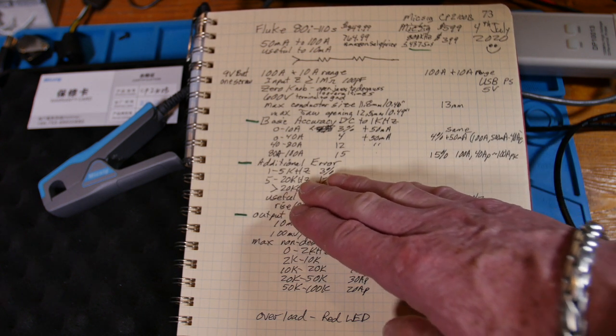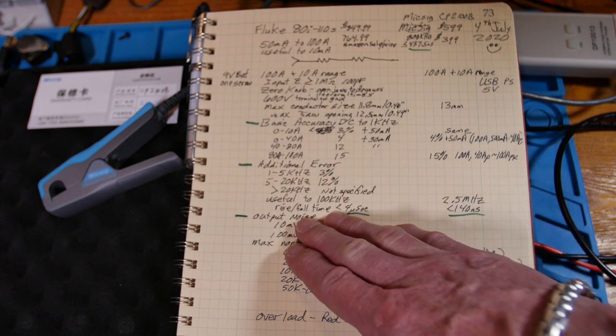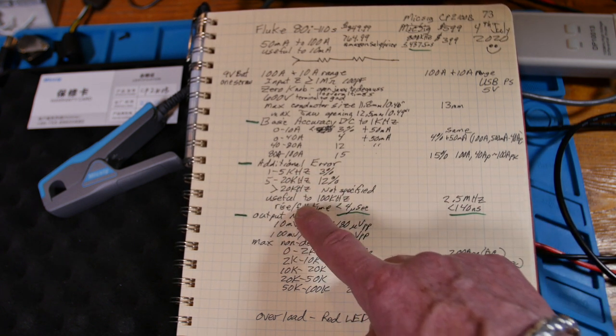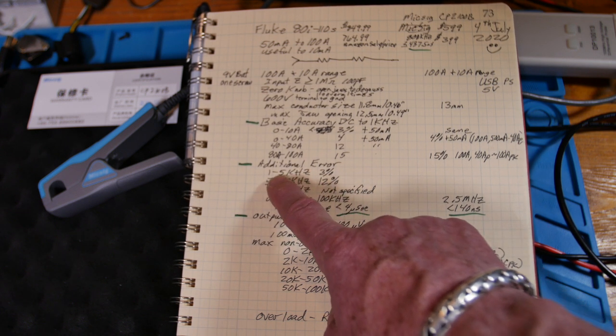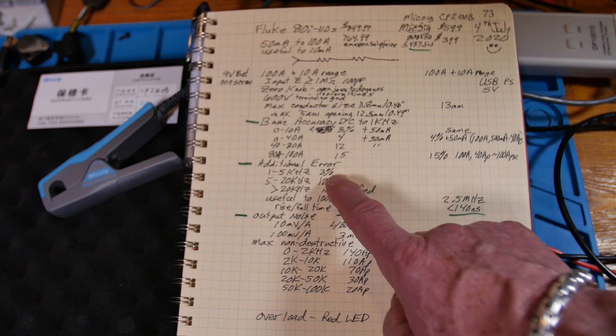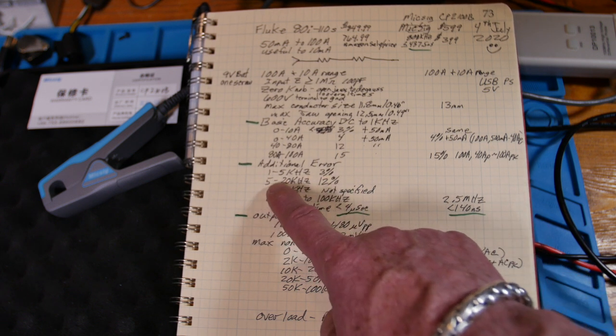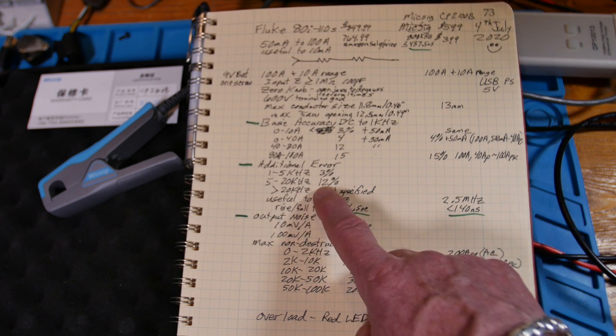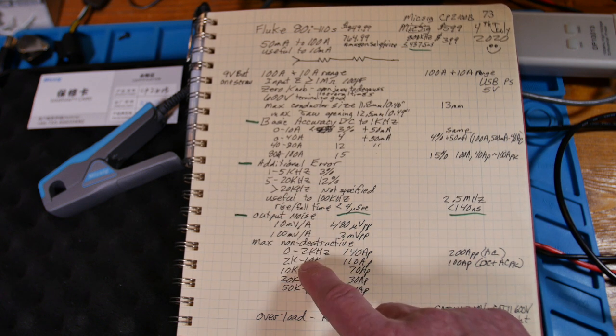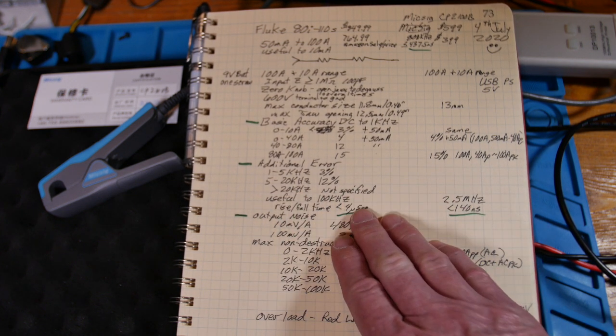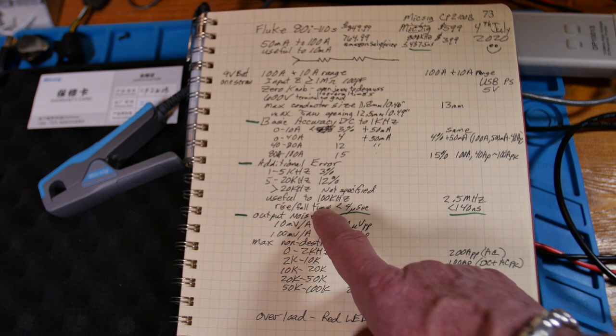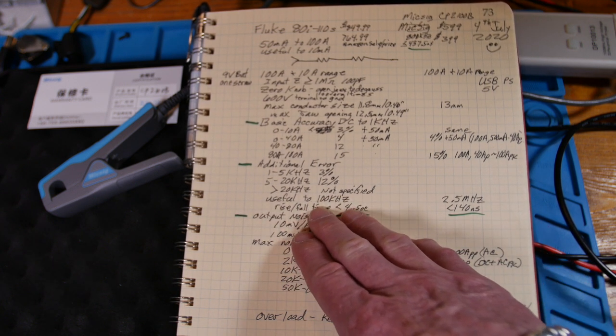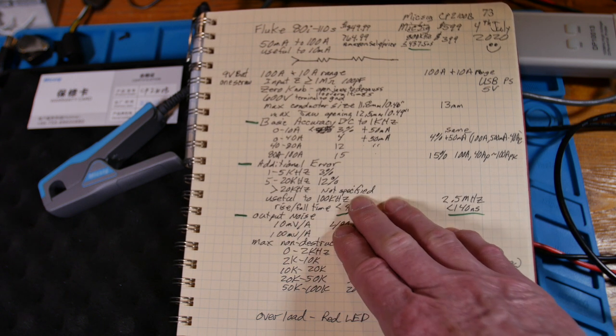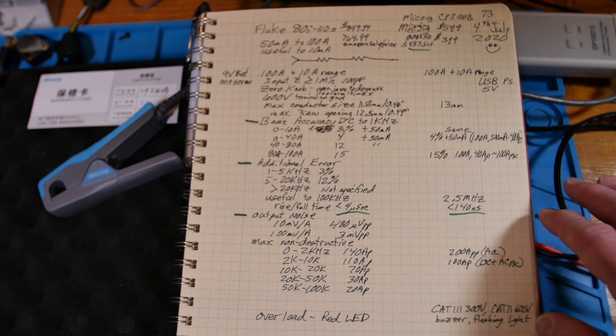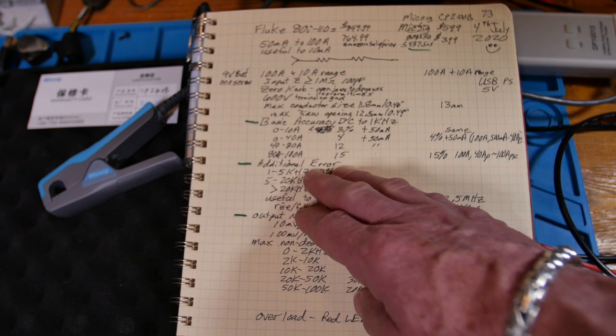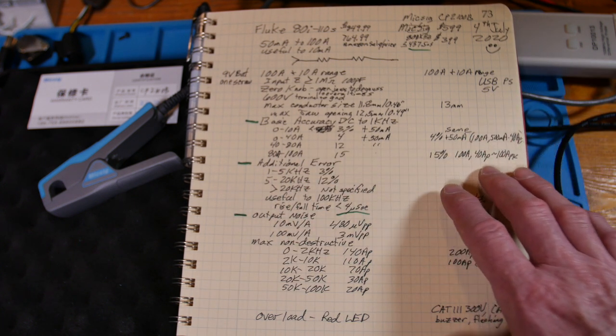And then on the Fluke, they have this additional error depending on frequency band. And you go 3% just from 1 to 5K. So that makes it not quite as good as a Micsig. And then 12% additional error for 20 kilohertz bandwidth. And then after 20 kilohertz, it's not specified. It says useful information to 100K. I don't know what that really means, useful information. But this guy is spec'd. They don't have this additional error, all this stuff. This guy's much wider bandwidth.